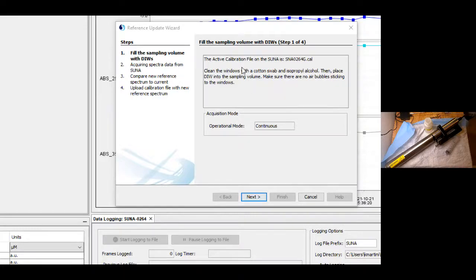Then I place the DI water into the sampling ball thing, and then make sure there's no air bubbles sticking to the windows. If you don't get a good reference spectrum, that's often what happens, and you can just stick the other clean end of the Q-tip in there to kind of dislodge the bubbles, probably using a flashlight as that. You don't ever want to look into it when it's on really closely because that is UV light. As we know, UV light is damaging.